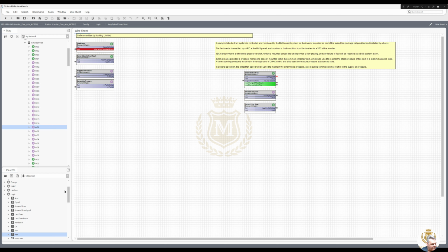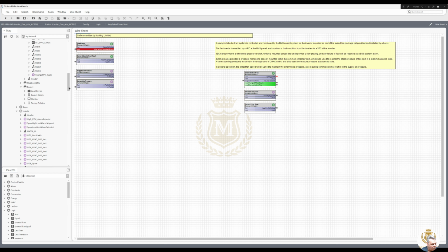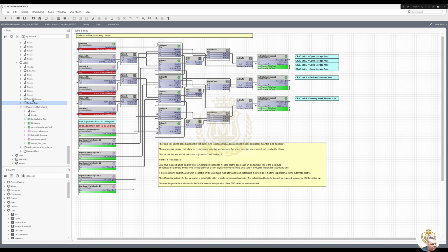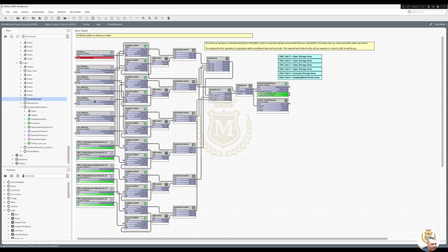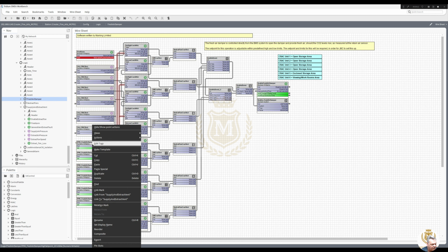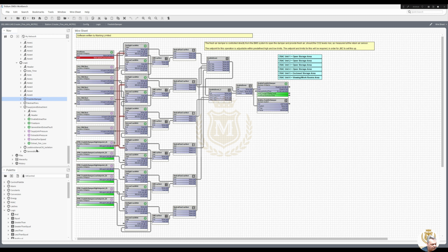I know I'm going to be needing at least one set point adjust, so I'll just take one from some logic that I've already done, save me rewriting it. Doesn't matter really what it is. It's because this is going to be in pascals. They're in temperatures and they're in parts per million. But let me just take one of these. That's not that one. I want one of these. Copy. Paste that into there.